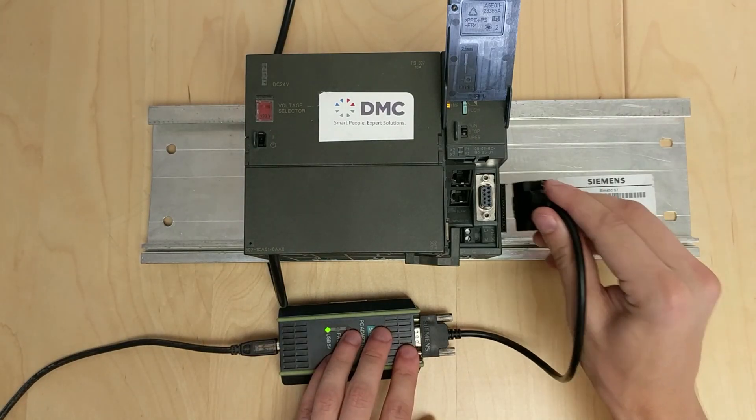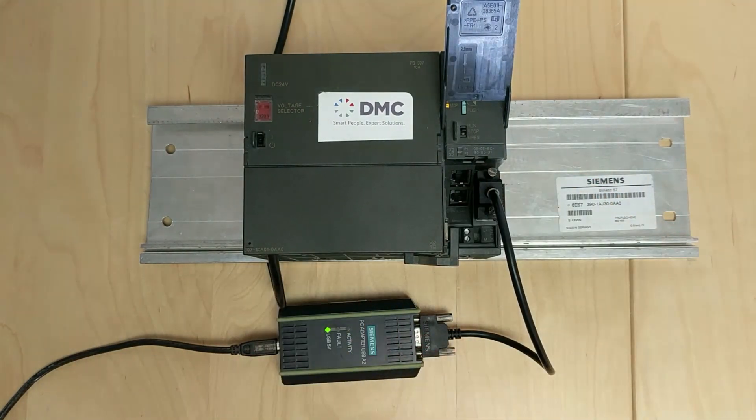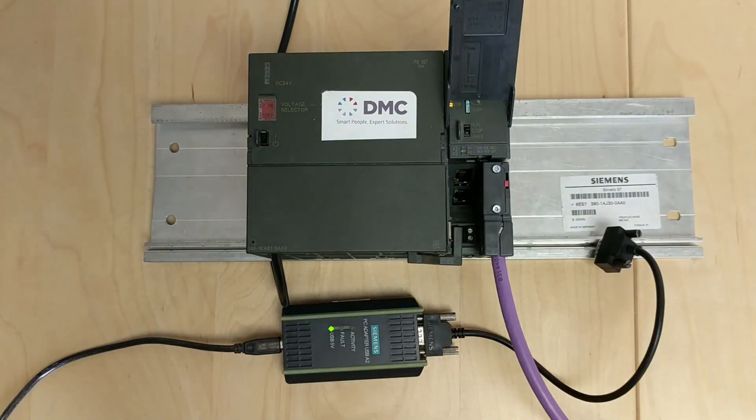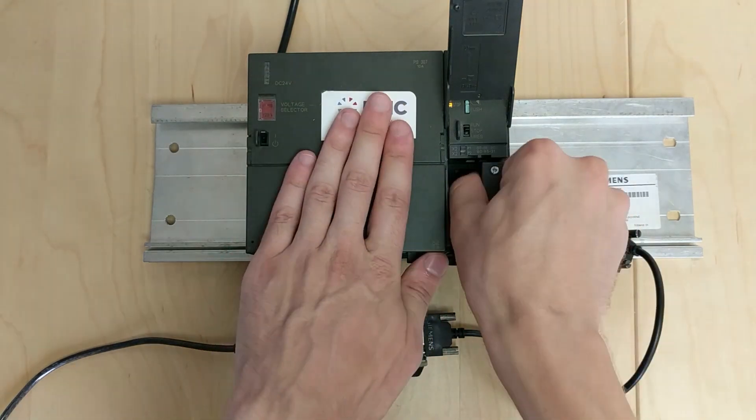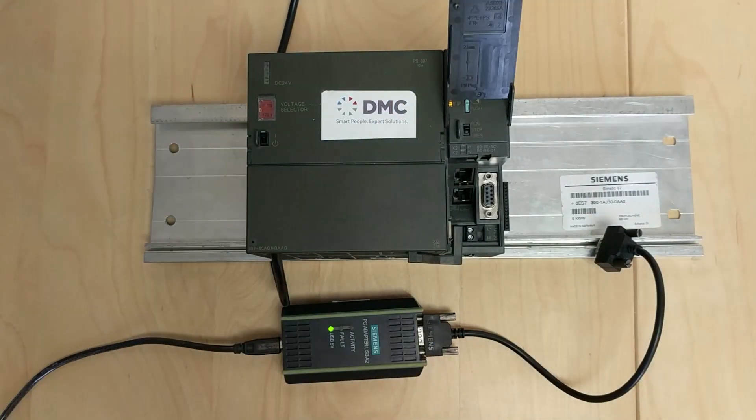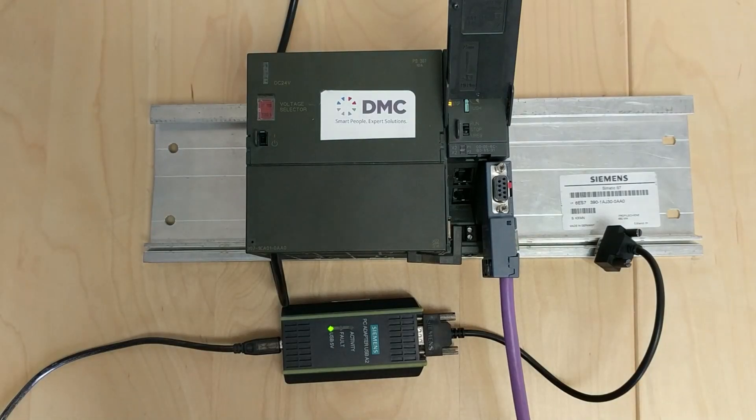First step is to plug into the PLC. As an example, I'll be using a Profibus connection, so I'll plug into the Profibus spot. If there is an existing Profibus cable, remove it and plug in there. However, if you don't want to take down the network, you can install a piggyback connector or plug into one of those.